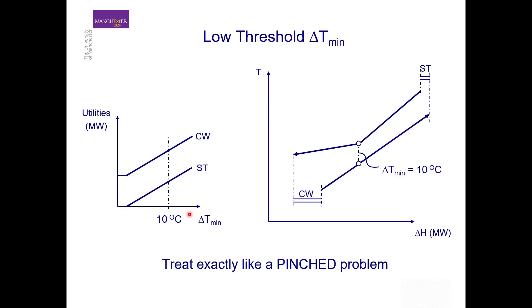Let's look at the case where we have a low threshold delta T min that is actually well below the most normal delta T min used in our processes, like 10 degrees centigrade. If we draw our composite curve we can see that we have requirements for both the steam — the hot utility — and the cold utility, if we are designing this process at a delta T min of 10 degrees centigrade. So although this is a threshold problem, the heat exchanger network design in this case can be treated exactly as a pinch problem.